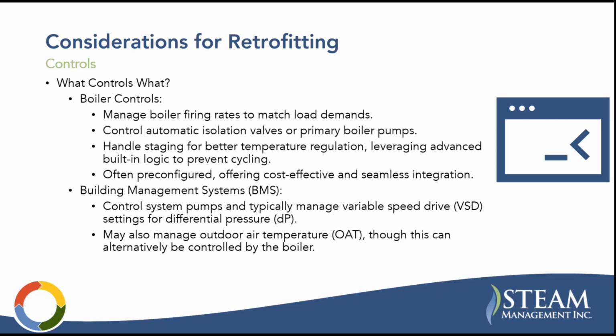What is your building management system going to control? It may control the system pumps and the VSDs, although those can also be controlled by the boiler controls in many cases. It may also manage the outdoor air temperature reset, but this can also be controlled by the boiler. So generally speaking, I would say you want to let the boiler control as much as possible, but that needs to be evaluated on a case-by-case basis.